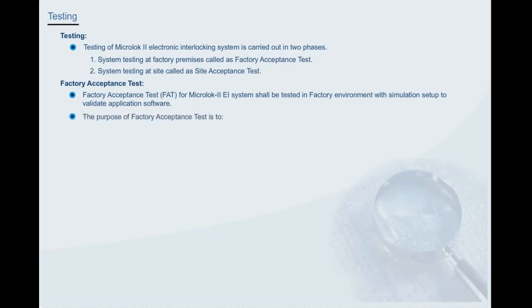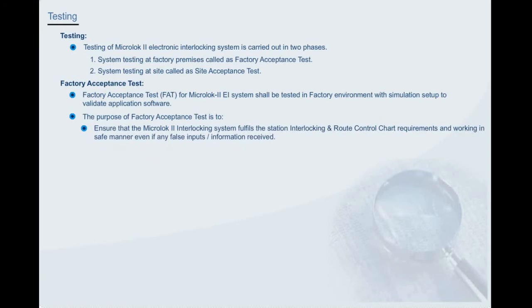The purpose of factory acceptance test is to ensure that the Microlok II interlocking system fulfills the station interlocking and route control chart requirements and working in safe manner even if any false inputs or information received. Minimizes the site errors and risks and reduces the corrections at site. This results in saving of time at site testing.